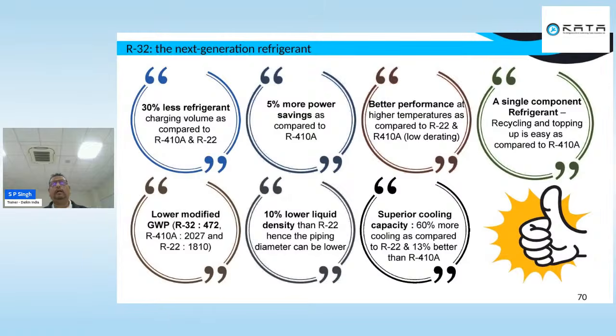If we start using R32 refrigerant, compared to R410A or R22, that means a 30% lower refrigerant charge. You also get about 5% saving in electricity, because the refrigerant effect is quicker, giving better performance, even at very high temperature. If you see the graph for R22 and R410A, R32 at very high ambient, let's say around 50 degrees centigrade, has comparatively much less derating than R410A or R22.